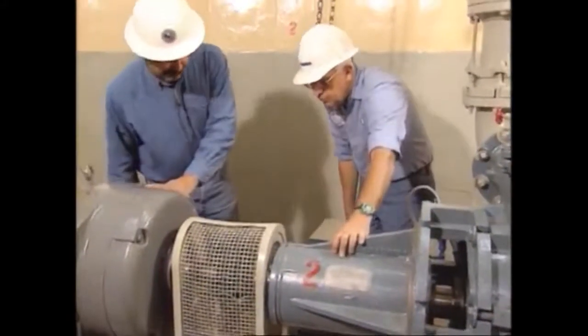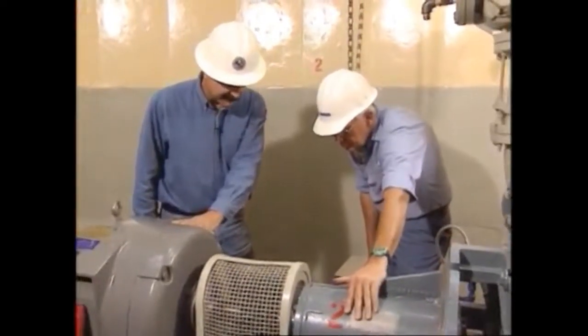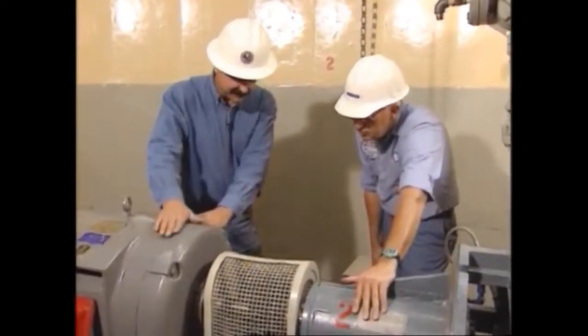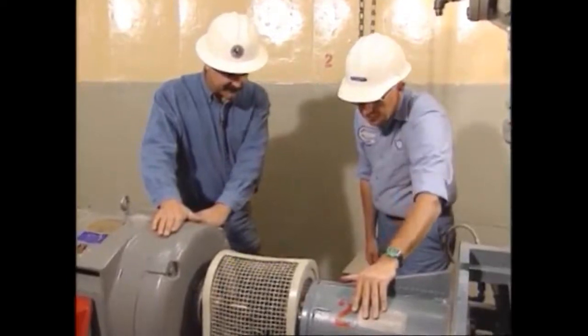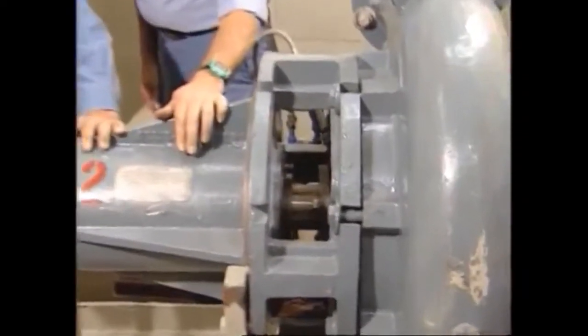Insulation failure can occur when deposits of dust, grease, or other foreign material accumulate on the windings and prevent the dissipation of the heat generated in the motor winding during normal operation. One solution is to keep motors clean.